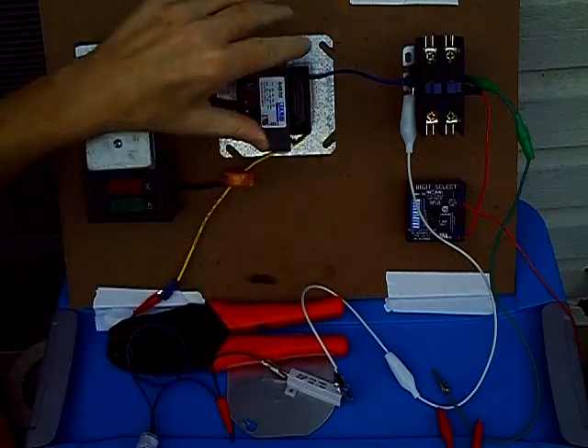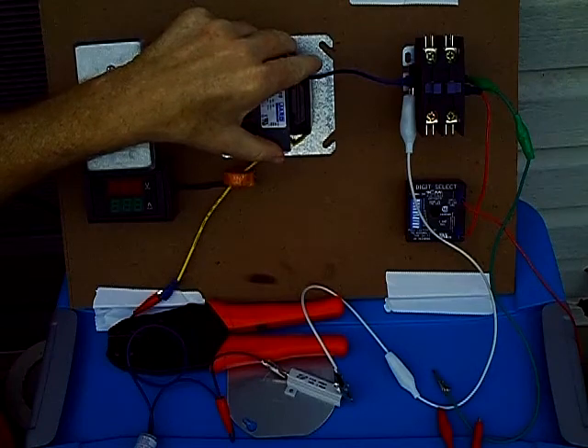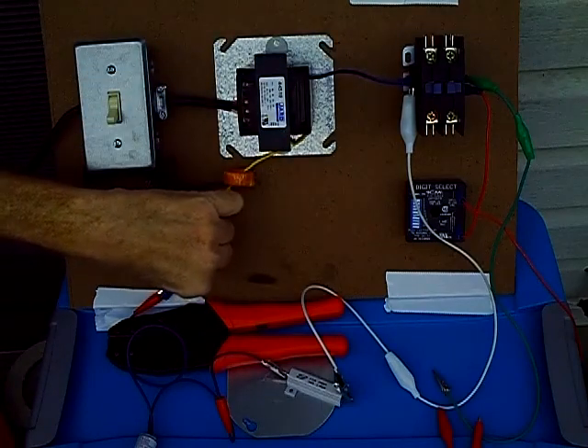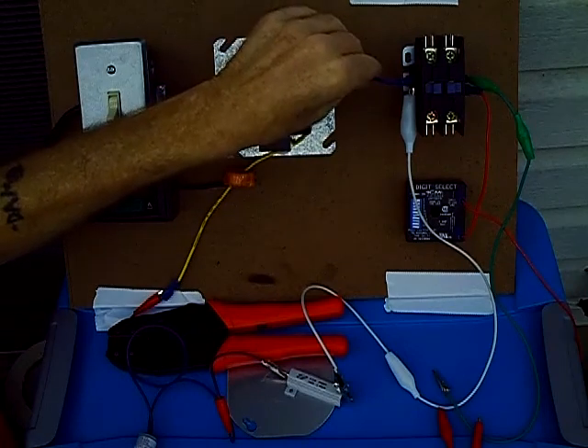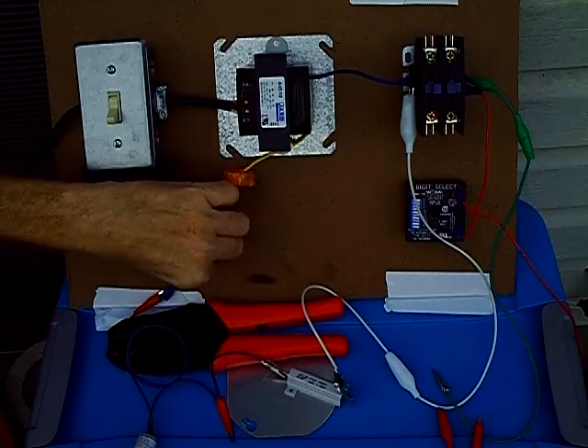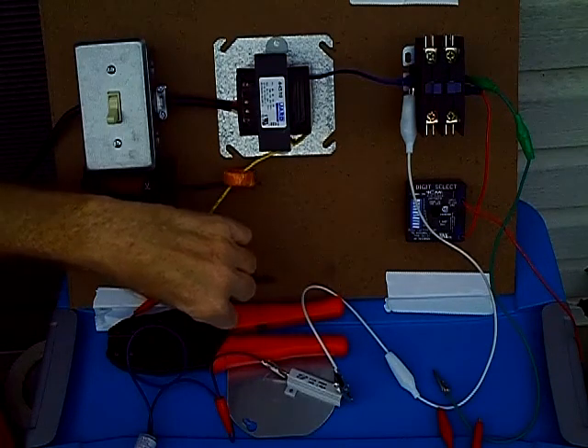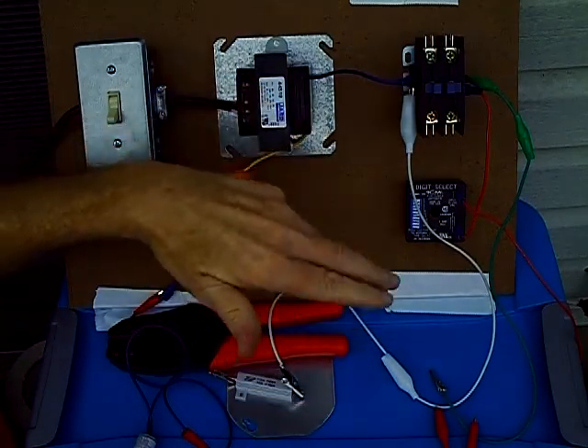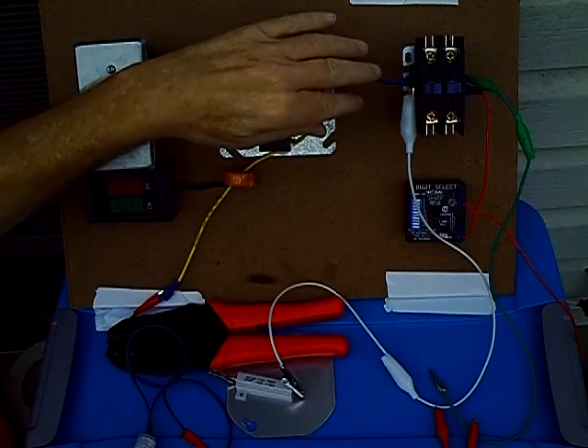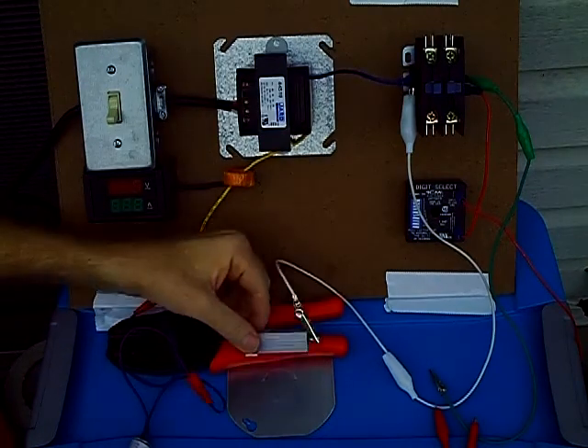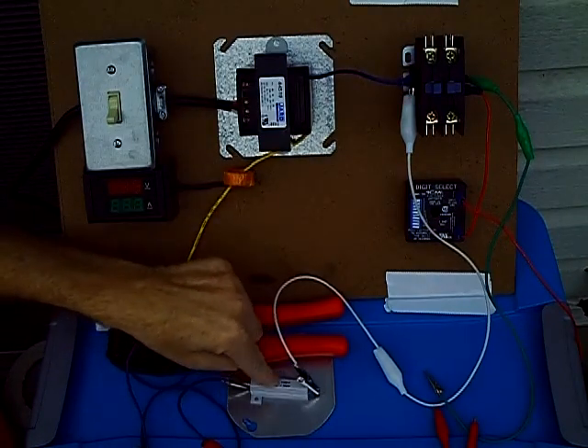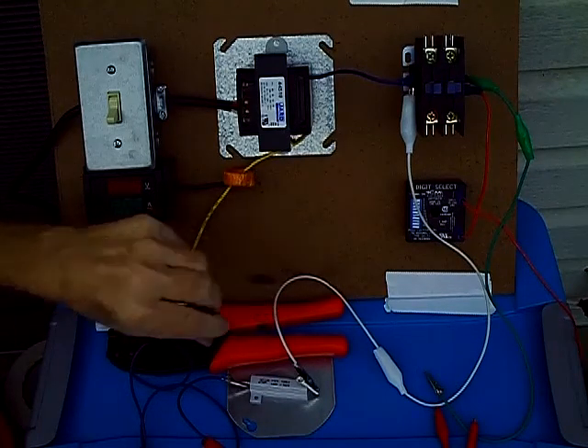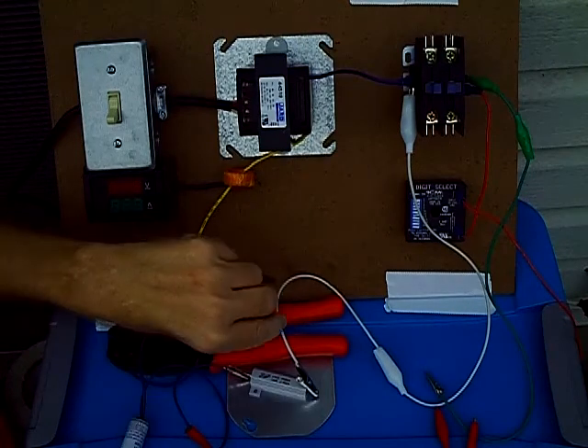What I've got wired in here, and just to do a quick lesson to wire this in, there's two wires coming out of the secondary to this side of the transformer. It's a blue wire and there's going to be a yellow wire. Now let's just pretend this is like a car battery. We'll say the blue wires are negative and the yellow wires are positive. You'll notice everything afterwards coming out of your ShortPro tool, it's got a red wire coming out of it. So we can maintain that as being the positive side, make it easier to understand how to wire it up. What I've done here is I've got this resistor that comes in the package right here, and I'm going to simulate the 1.5, 1.6 amp current draw across the circuit just to show that the ShortPro tool can find that short and how long it takes to do that.